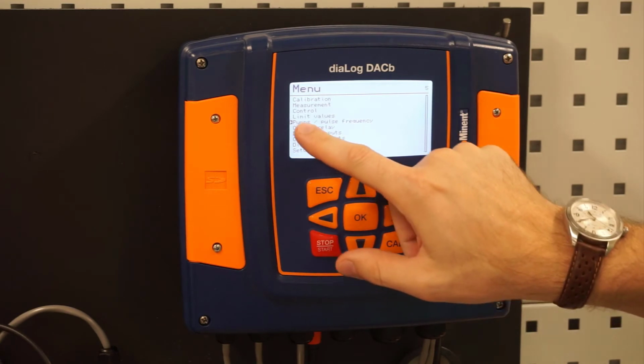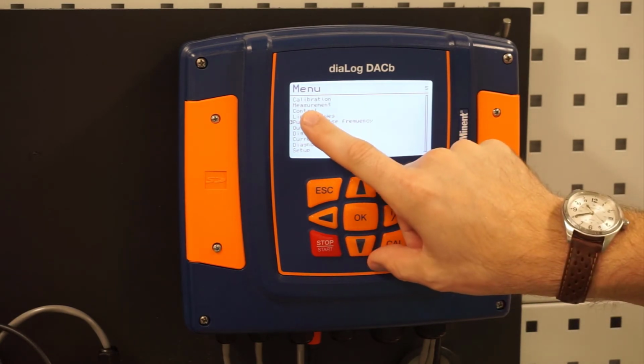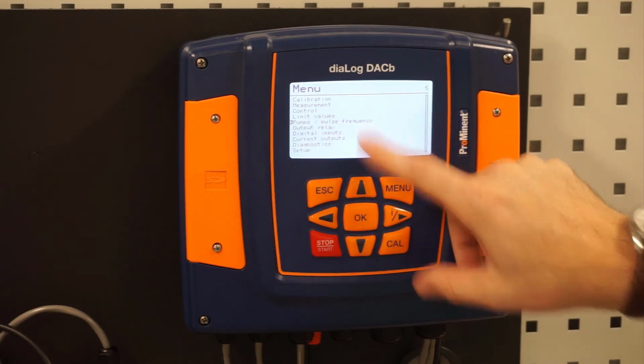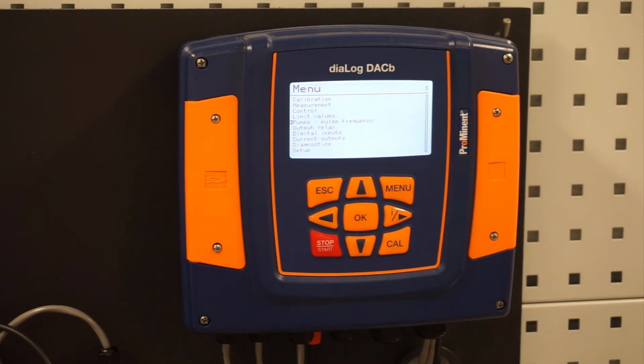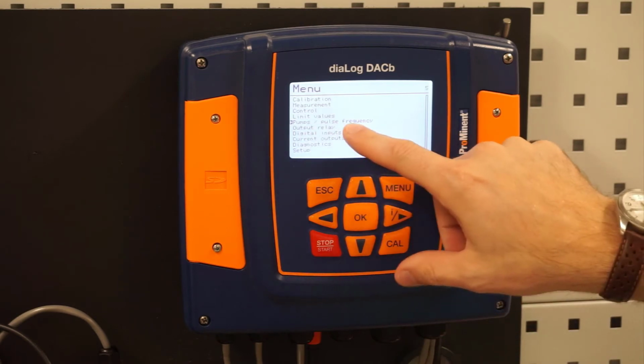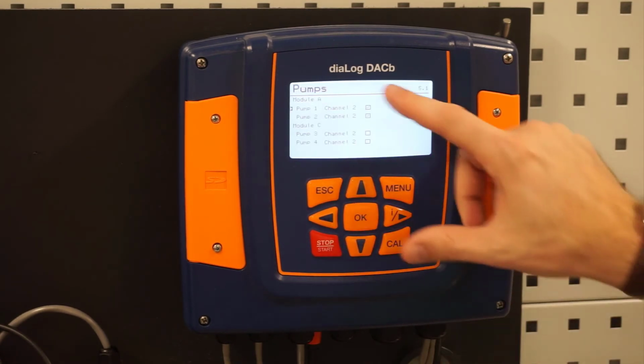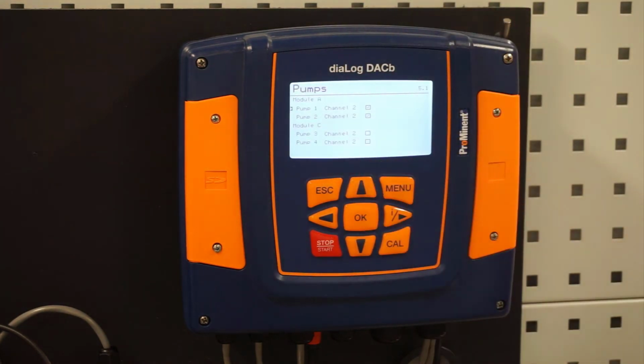This pump screen would only be used if we set up control and if we're using those digital outputs, those pulse frequency, those contacts out. If we are using that, we would go in there and set up what pumps we have. Remember, we have 4 options for those, so you need to know where you landed your wires. We cannot land those wires for you because we do not know if you're controlling, what kind of pump you're controlling, or what that wiring looks like, whether it's milliamp or digital.